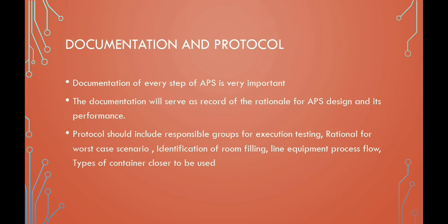The protocol should also cover the types of container closures to be used, fill volumes, minimum number of units to be filled, line speeds, and type of media to be used. This protocol shall be prepared prior to starting the study. It should also include personnel training requirements, details about batch records to be used, and documentation requirements for the final reports.